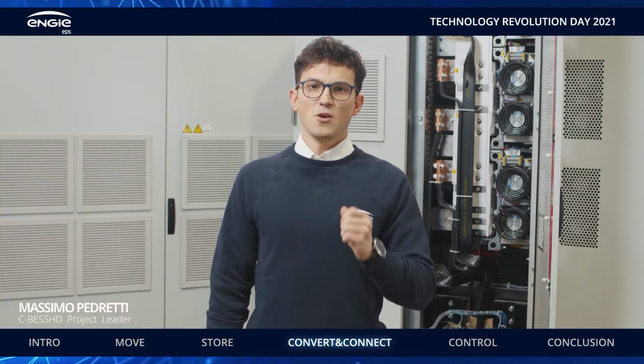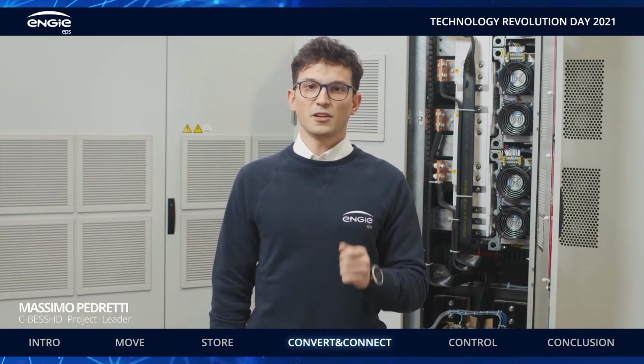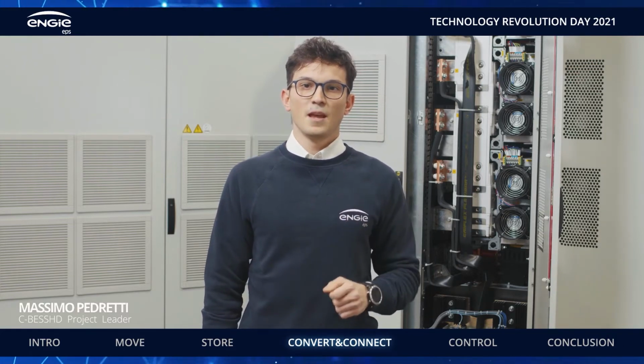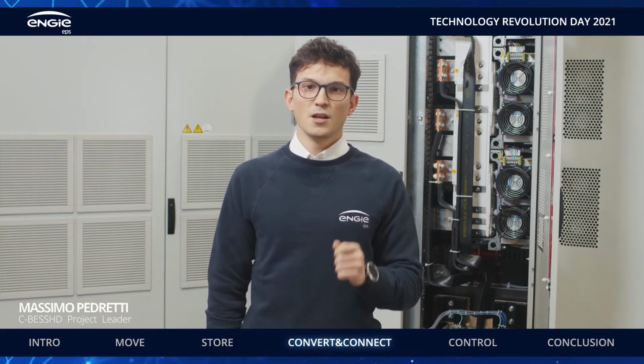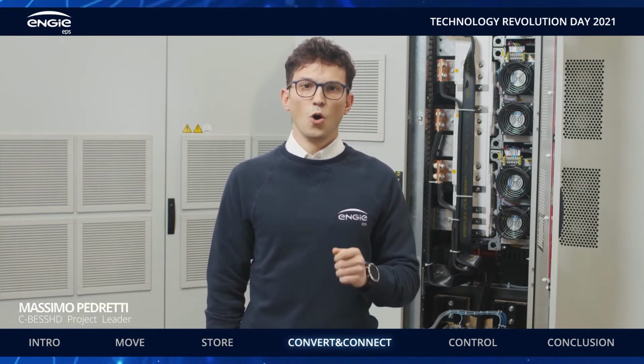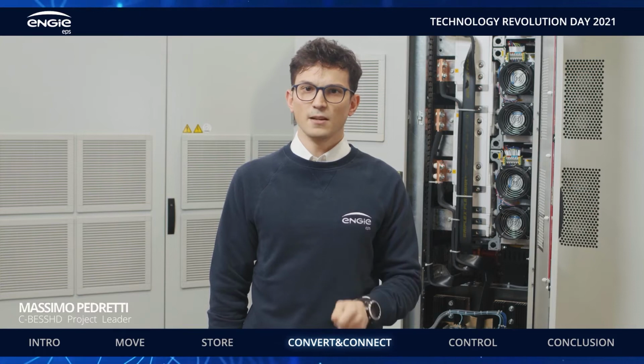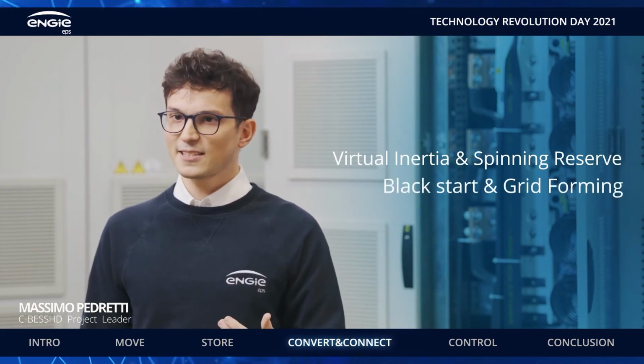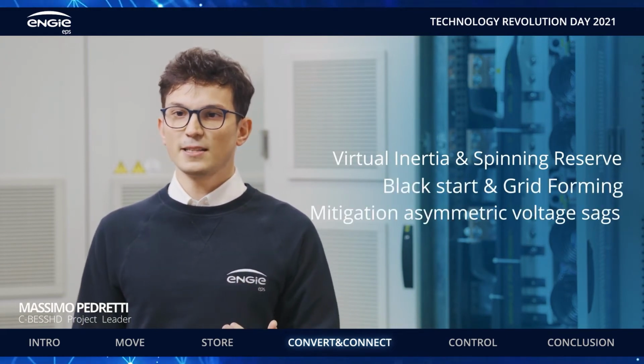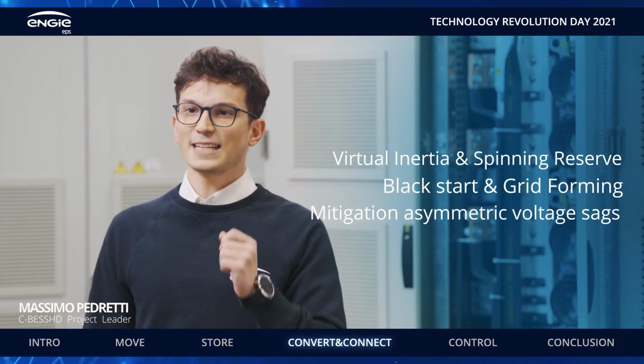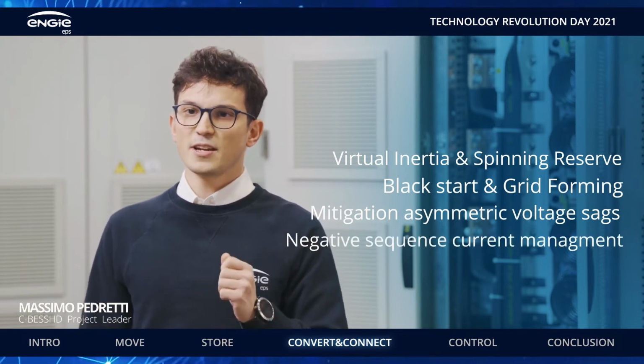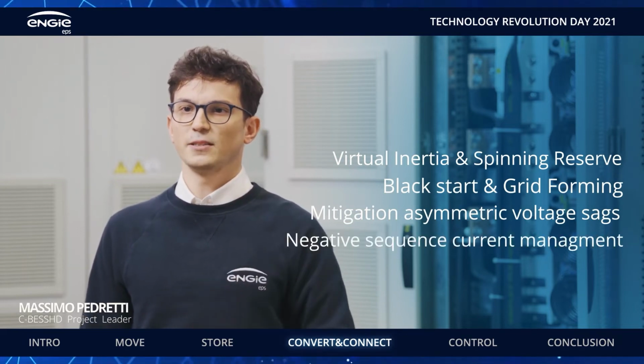We have been pioneers in innovative inverter functions for microgrids. It's time to introduce new advanced features also for utility-scale grid-connected plants, such as virtual inertia, spinning reserve, black start, grid-forming capabilities, and mitigation of asymmetric voltage sags with negative sequence current management.